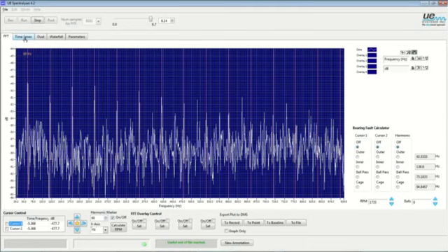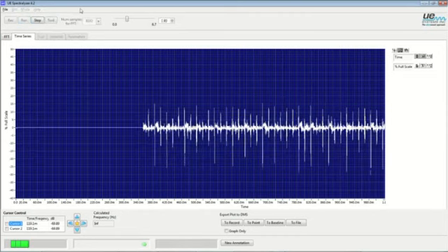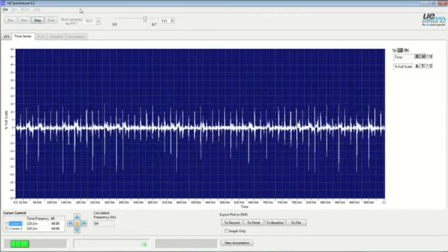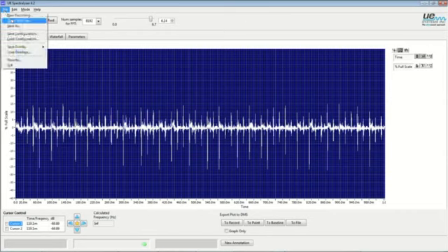That's in the FFT. In the time analyzer, what we see here is uniformity and consistency. That's a fairly uniform spectrum there, despite some deviations in the amplitude. So on pure corona, it's really easy to spot. You have the normal sound that we're accustomed to hearing, and we're looking for those two things on the frequency display: every 60 hertz harmonic and the abundance of frequency noise.